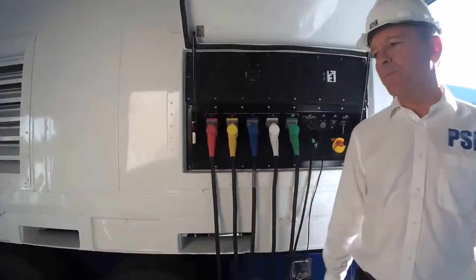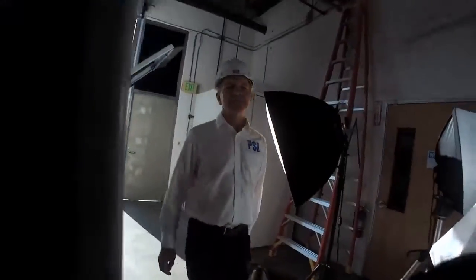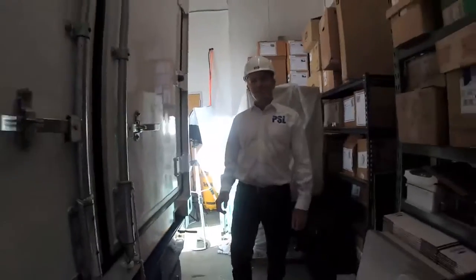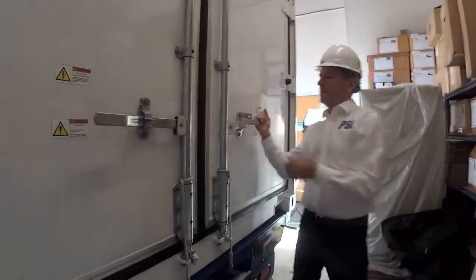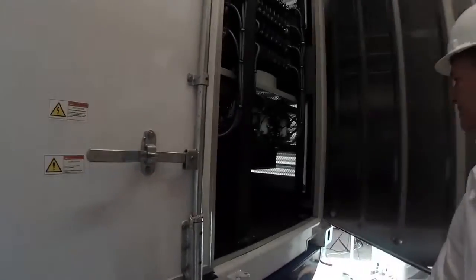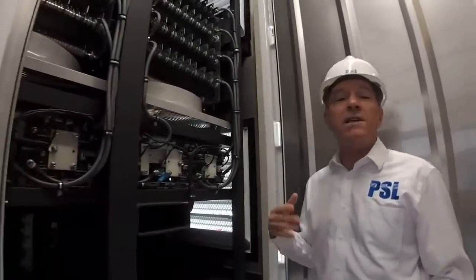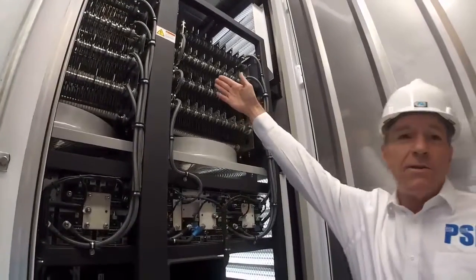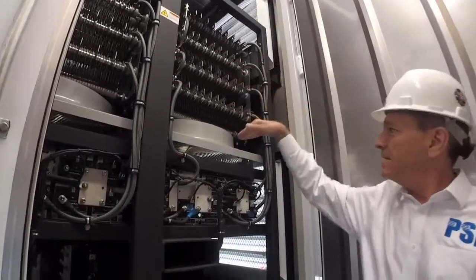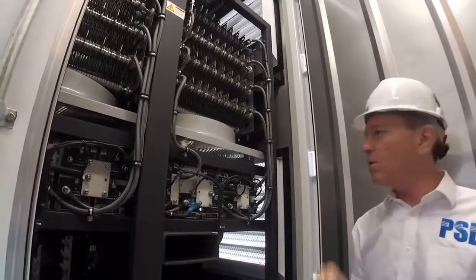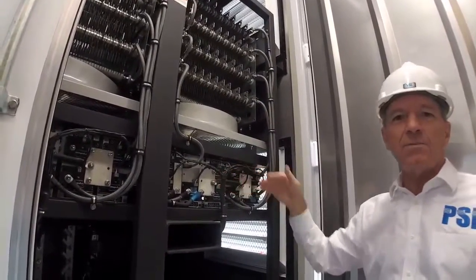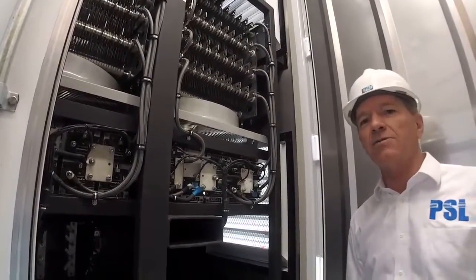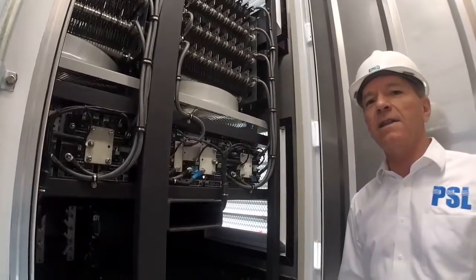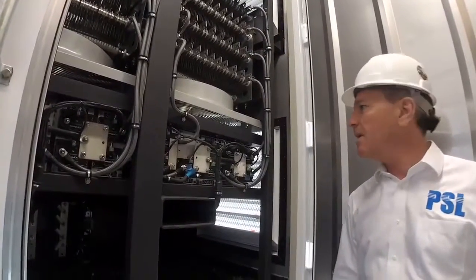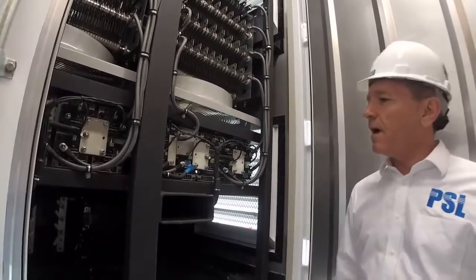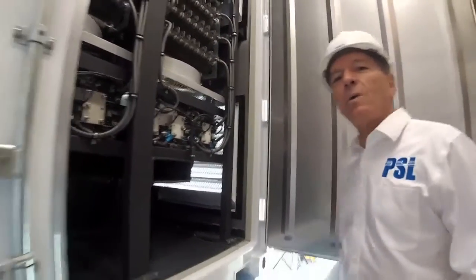Let me show you the load bank. This is the business end of the Grid Thumper. As you can see, it's a three-phase load bank where these are the resistors and cooling fins, with large fans, one for each phase to keep it cool. These are the solid-state relays, precisely controlled and time synchronized with GPS, with control latency of less than 1 microsecond. Again, there are safeties throughout this system to make sure it works well when we expect it to.